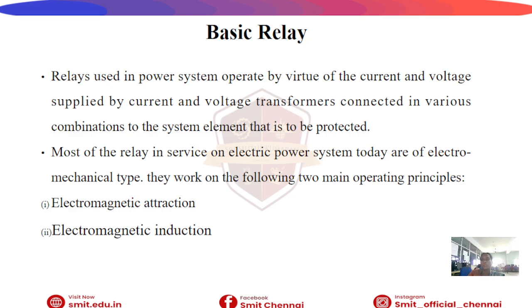Protective relay. A protective relay is a device that senses abnormal conditions using current transformers and potential transformers. Most relays used in power systems are electromechanical relays, operating on the principles of electromagnetic attraction and electromagnetic induction.